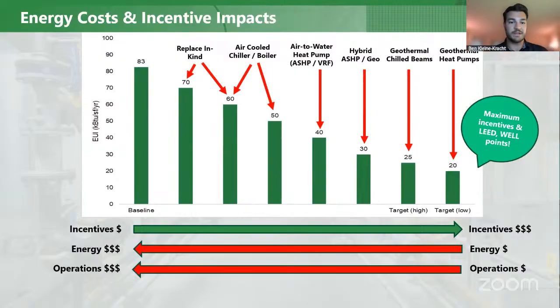So we have a EUI chart on screen, and these are kind of the ranges you'd expect these four options to be in. Geothermal heat pumps, the 20 is probably a little bit of a high range — we've seen them perform anywhere from 17 to 22 EUI. For the geothermal chilled beams, you could expect slightly higher, probably around 22 to 25-ish. The air source heat pump and hybrid geo, you could expect around 30 to 35-ish. And then following that would be the air to water full air source heat pump. Typically for zero energy schools, the big number is 25 EUI, which is what we want to be at to fit all the PV on the roof.